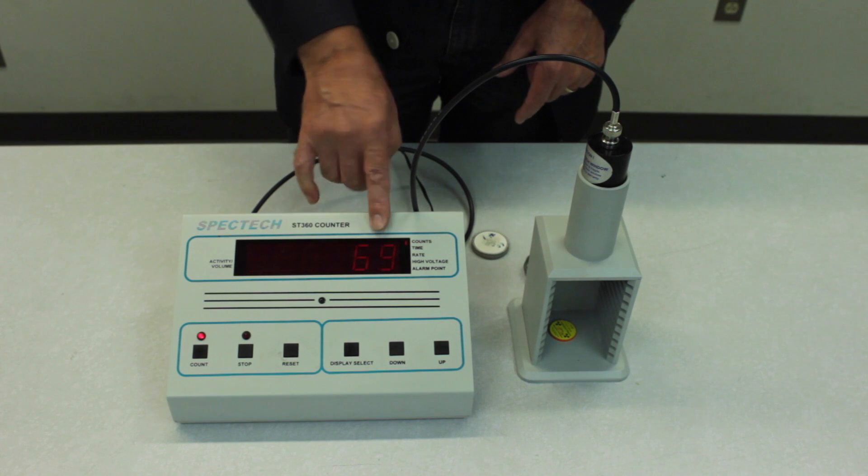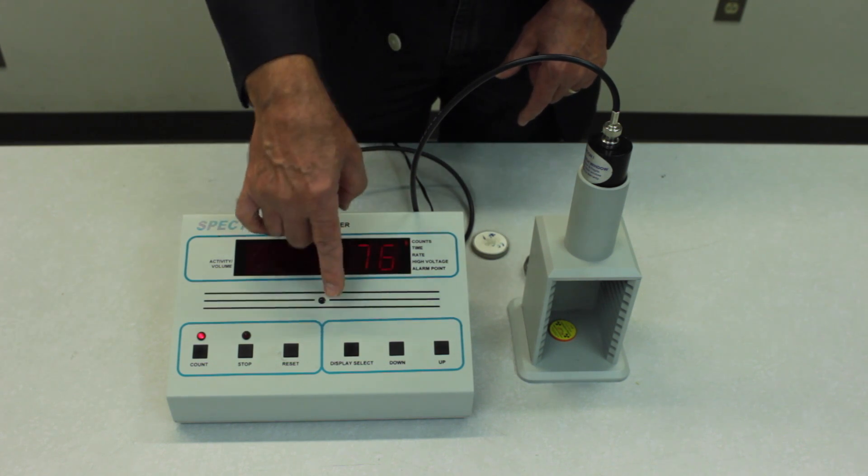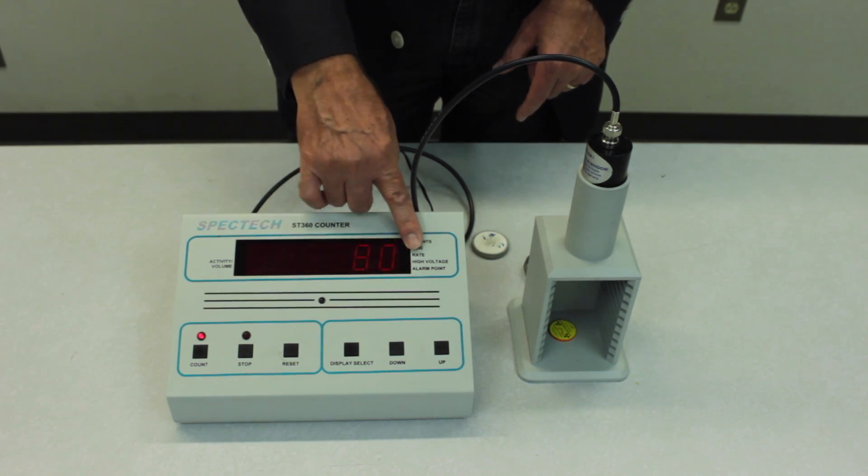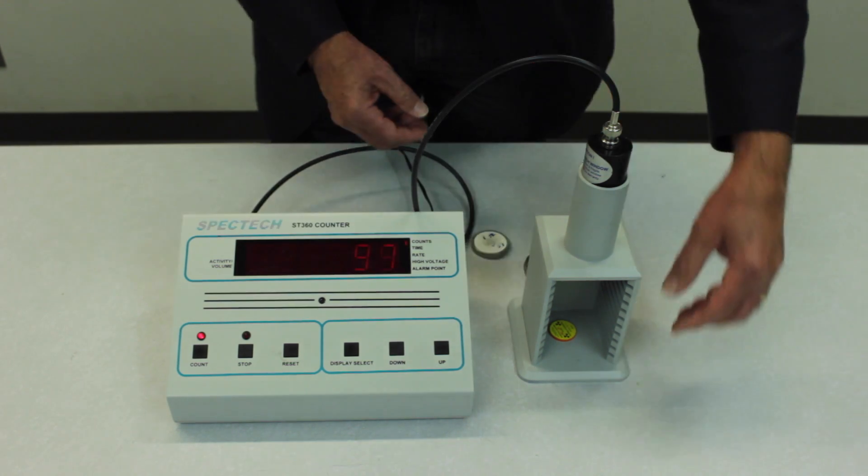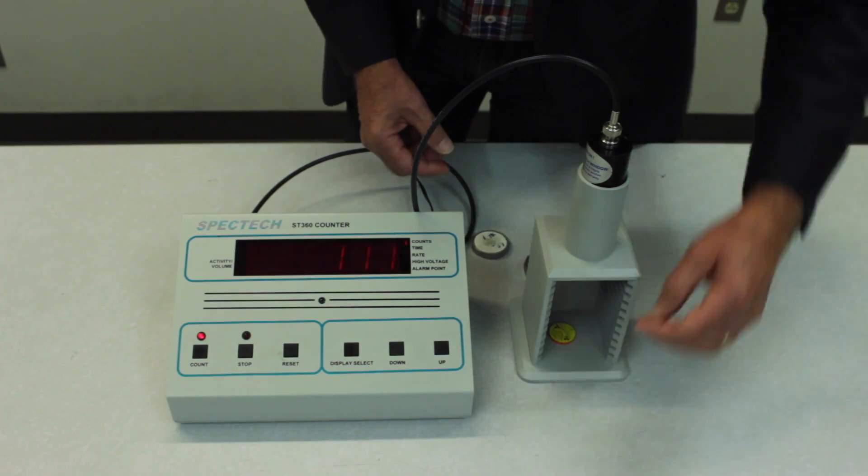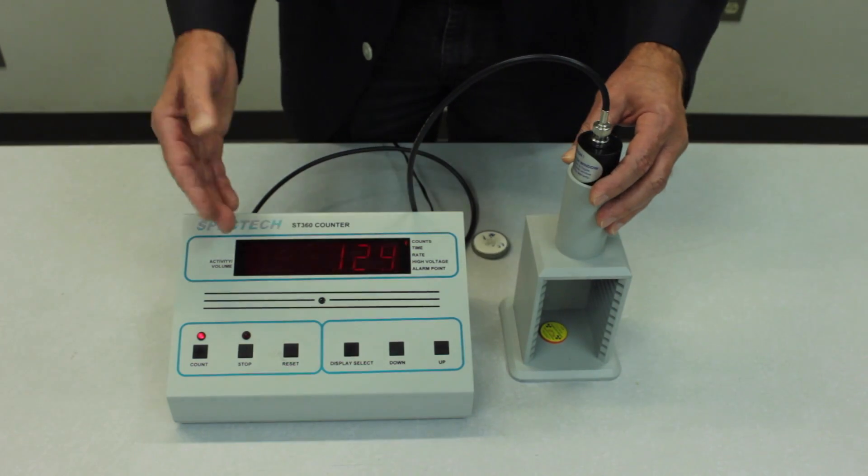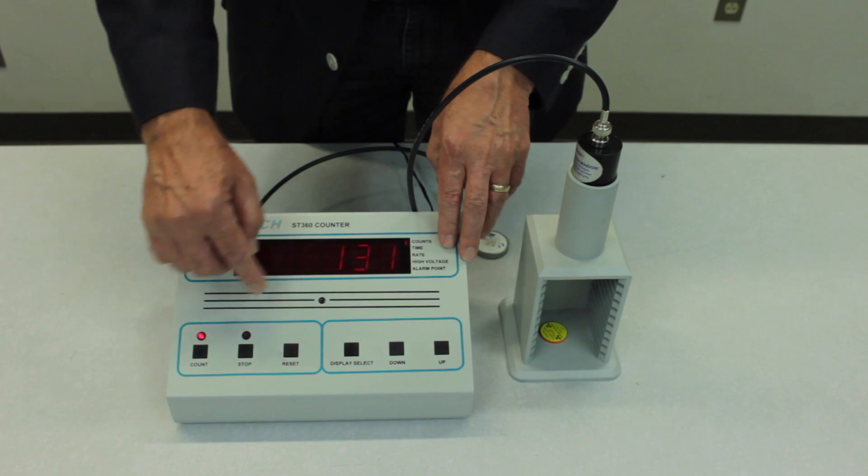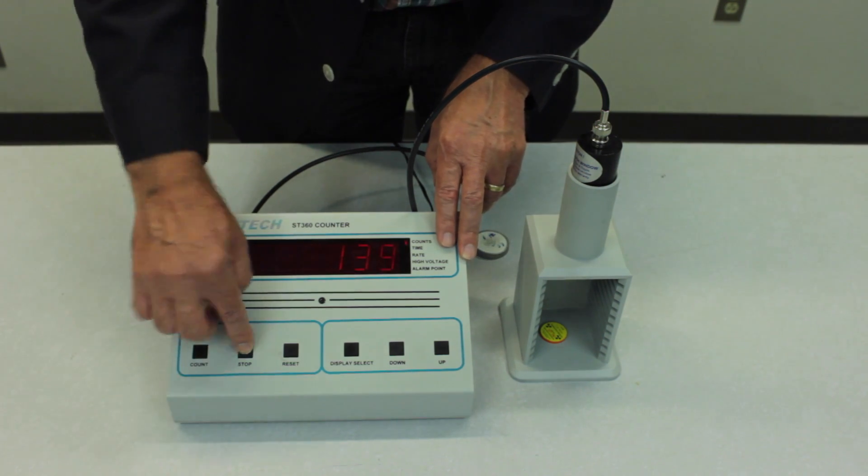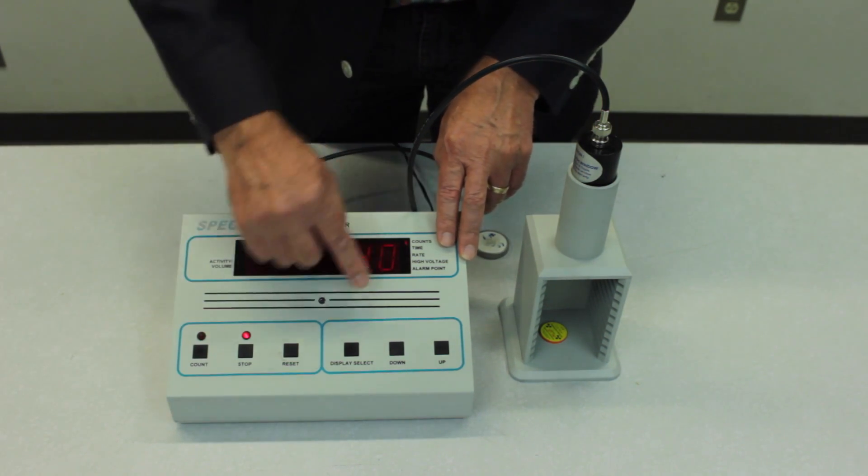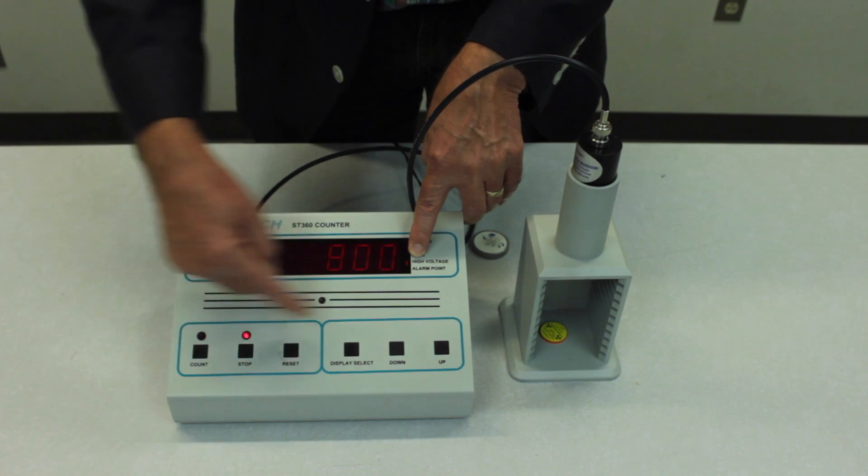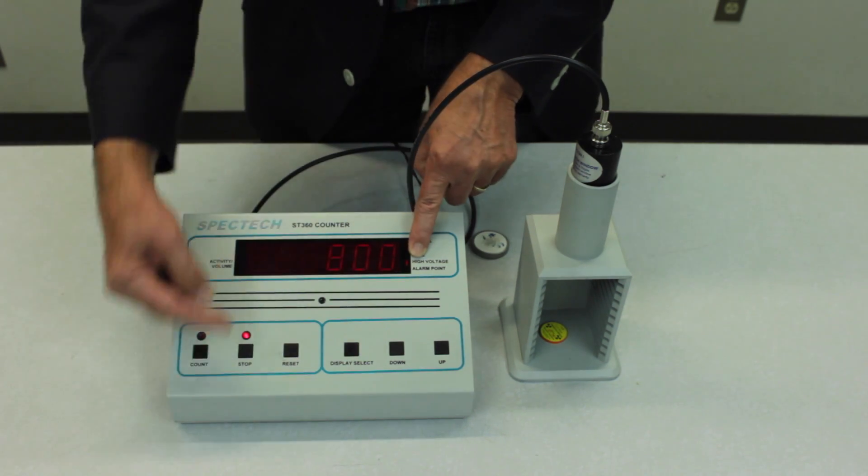So what you want to do is to adjust the voltage applied to the tube until you just begin to get some counts. And then increase in increments of twenty volts until you reach the breakdown region. So let me just stop this and go back to the display select function down to the high voltage. And I'm going to reduce this down to six hundred volts.